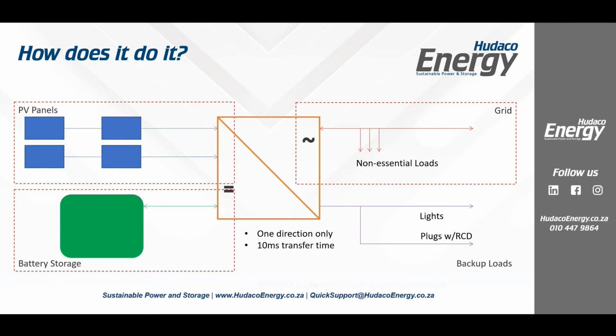Okay, it's 10 milliseconds. We do have a digital out option for load control, which we're not going to cover today. That we would cover in the more advanced setting. In fact, I think there are 4 DOs and 1 or 2 digital ins and digital outs. Analog in and out. And those we would control loads based on a variety of factors: time of day, battery state of charge. We can receive signals from outside, almost like a ripple relay, depending on which area, which country you're in.